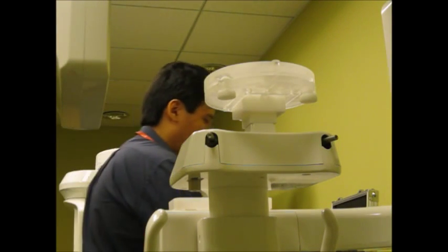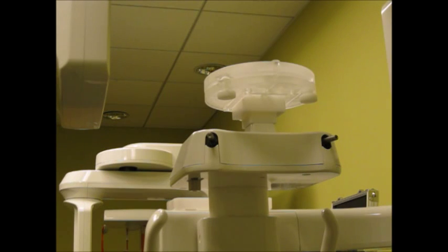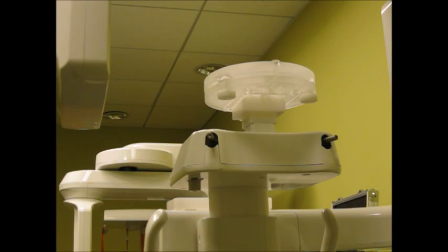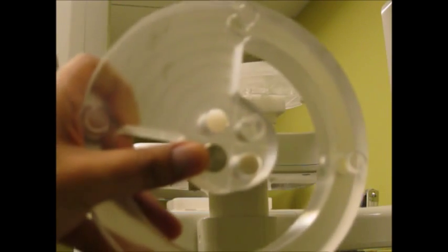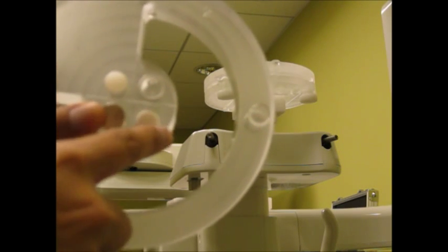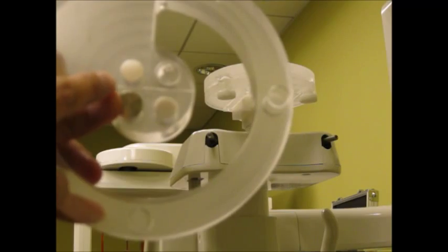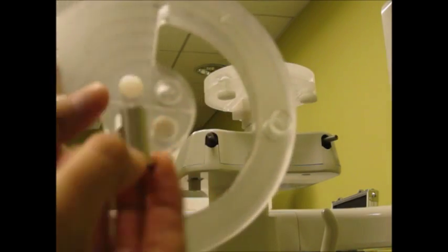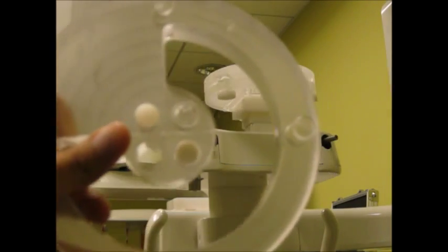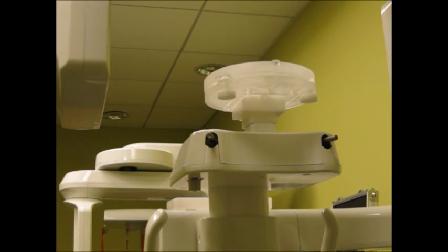Okay, if you use a card like this, you might see it more easily. Okay, you can see the laser beam now. Just make sure that that laser beam is right, as I said, right on the middle groove of that, like that. Okay, you can slide the jig as I just did. And then once you find the sweet spot, once you find that the laser beam is aligned, you can just tighten up those plastic screws, so that you can hold the jig in place.